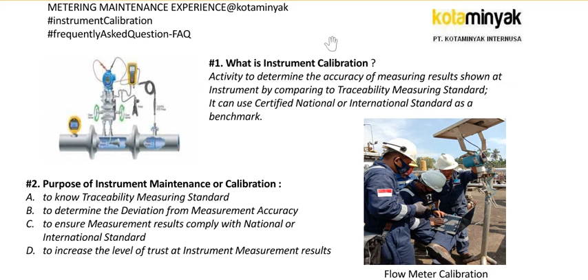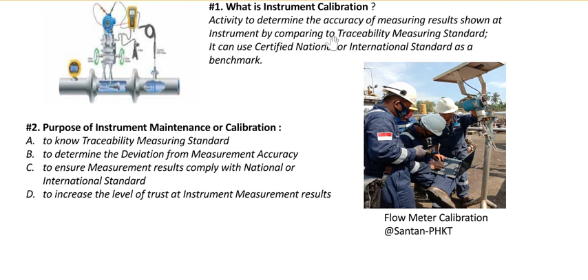What is the purpose of instrument maintenance or calibration? To know traceability measuring standard, to determine the deviation from measurement accuracy, to ensure measurement results comply with national or international standard, to increase the level of trust at instrument measurement results.